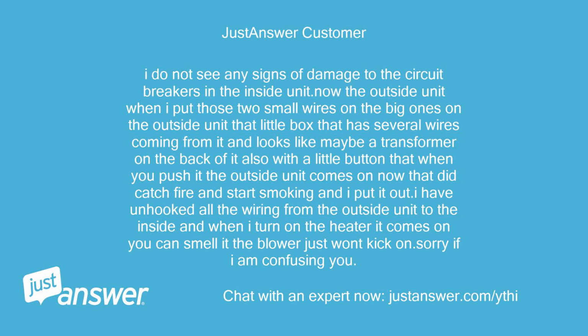I do not see any signs of damage to the circuit breakers in the inside unit. Now the outside unit, when I put those 2 small wires on the big ones on the outside unit, that little box that has several wires coming from it, and looks like maybe a transformer on the back of it also, with a little button that when you push it the outside unit comes on. Now that did catch fire and start smoking, and I put it out. I have unhooked all the wiring from the outside unit to the inside, and when I turn on the heater it comes on. You can smell it, the blower just won't kick on. Sorry if I am confusing you.